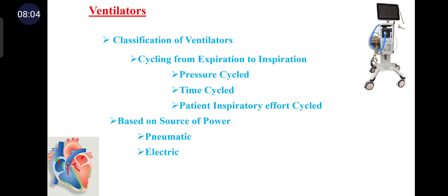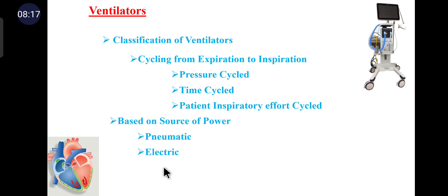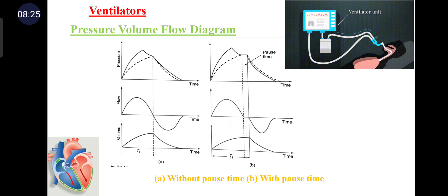Classification based on source of power includes pneumatic and electric. Pneumatic means the ventilator is powered by compressed gas, whereas electric means the ventilator is powered by an electrical device such as an electric motor or similar gadget.